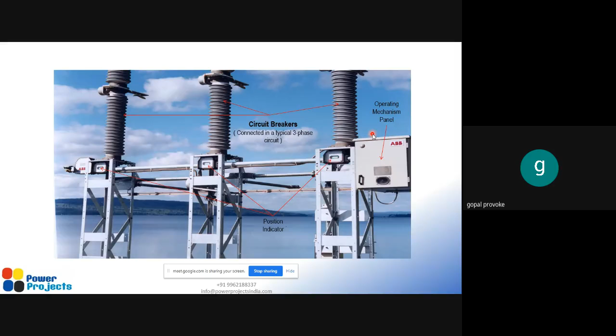And we also have a position indicator, and this will indicate whether the circuit breaker is open or closed. And we have the mechanism rod. This is a mechanism rod or a transmission rod, and this is used to perform the closing and opening operation. So we have the motorized control operation, and this will operate this rod for performing closing and opening of the circuit breaker. And this operation can be controlled from our control room or SCADA, so it can be controlled remotely. We need not go to the field to operate this circuit breaker. And similarly, the isolator will also be quite similar. The operation will be quite similar to that of the circuit breaker.